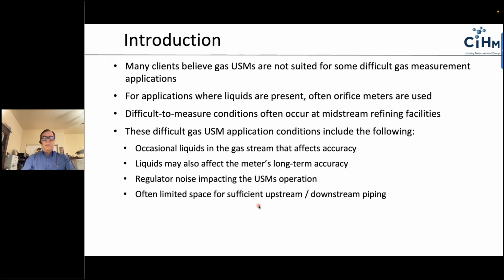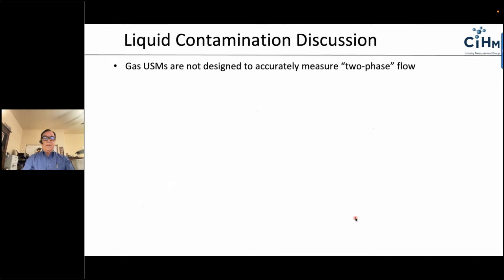Often limited space is available upstream and downstream because of the location where the meter is going to be installed in the piping. So we'll be covering an application with a very limited amount of space and show you some data that was collected at the TransCanada Calibration Lab last year. H2S is always a potential issue. In the past, transducer failure was very common. We also have to deal with potentially venting gas if we're using orifice meters. So we'll talk about ultrasonic meters and their use today with H2S applications.